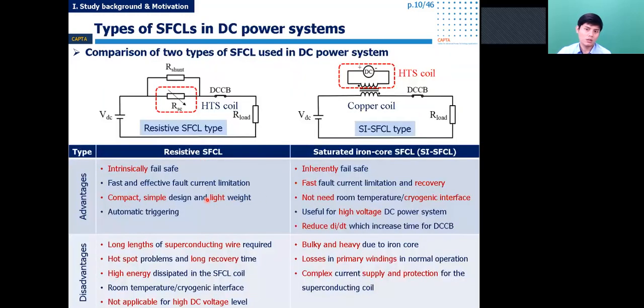Recently, most DC SFCL studies focus on the resistive and saturated iron core types. The resistive SFCL has the simplest and most compact design, and limits the fault based on the properties of the superconductor. However, it has an advantage only in low voltage systems. In the case of HVDC systems, with voltages over 100 kilovolts, the resistive SFCL is not applicable due to the current manufacturing technology of the superconducting wire.